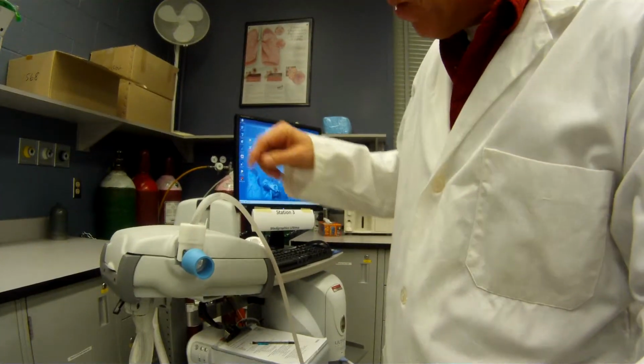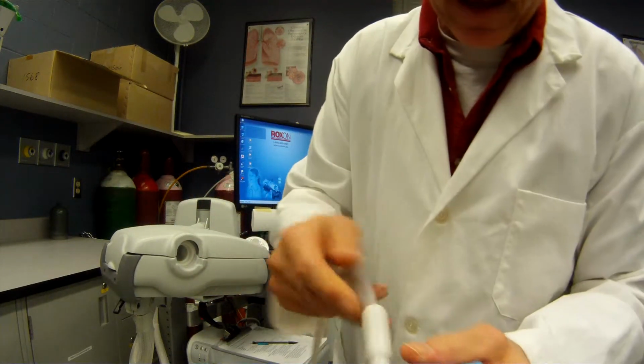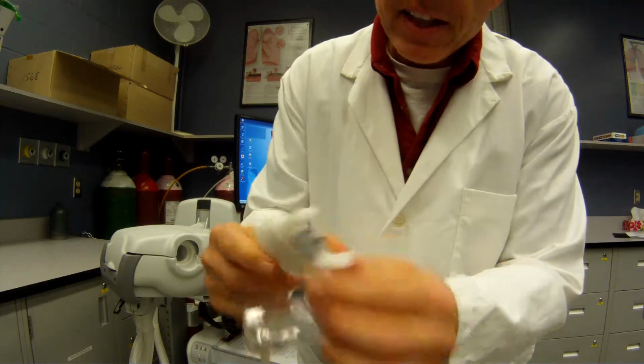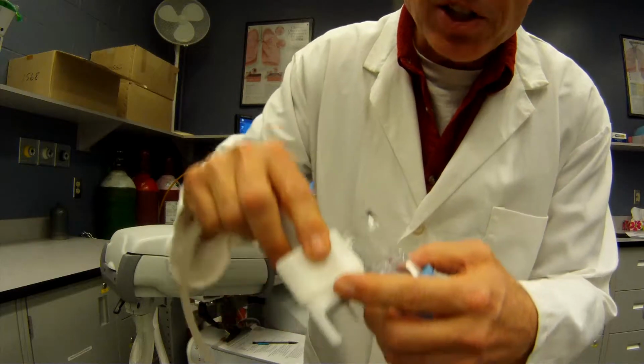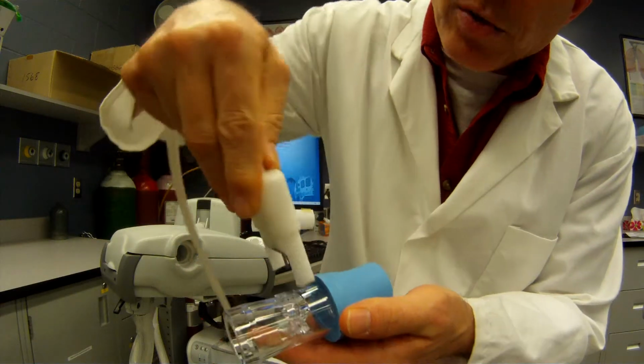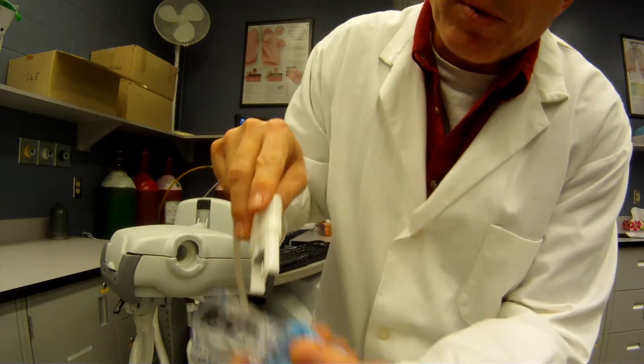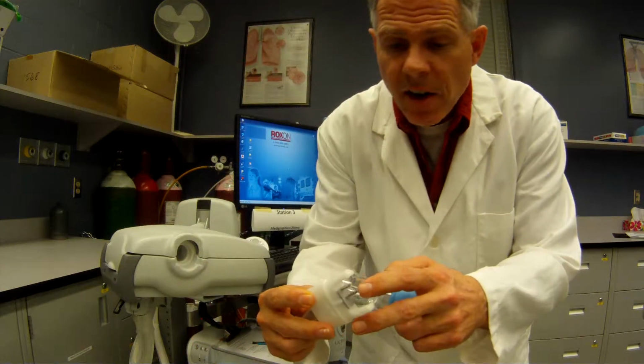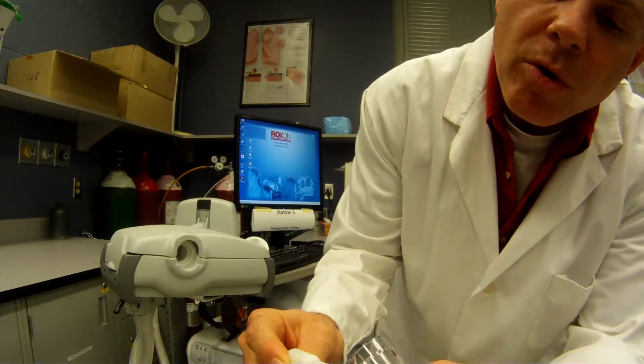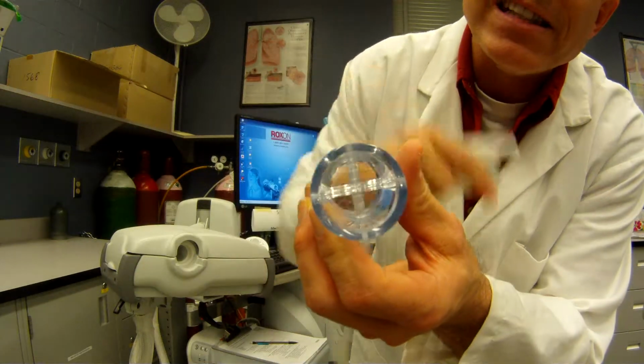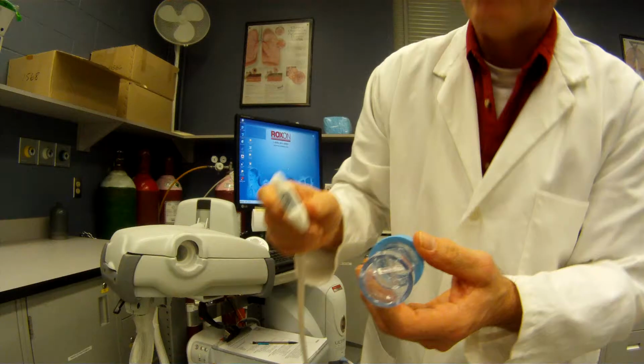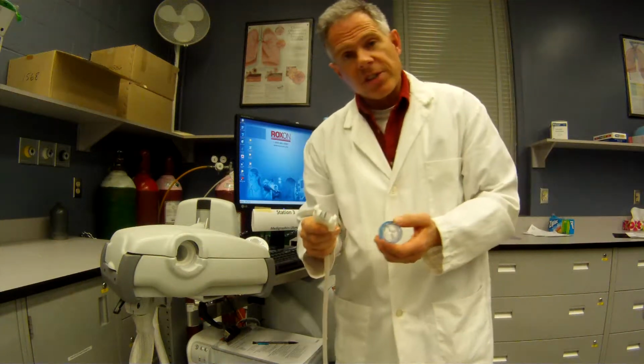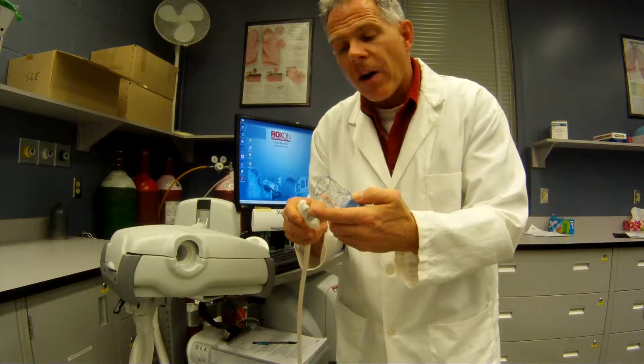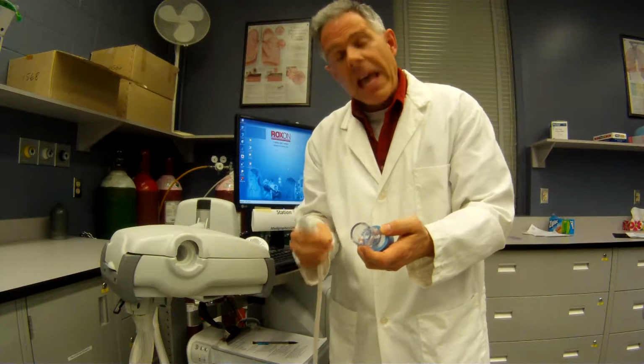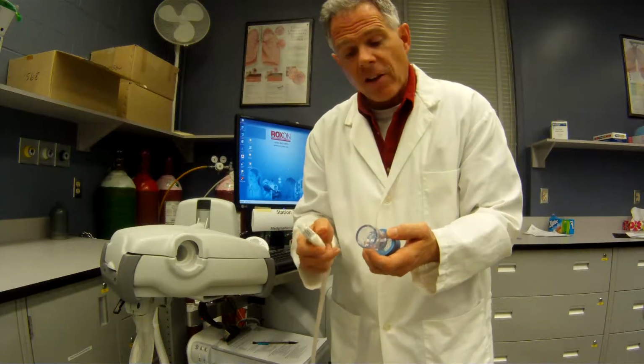Now, this little component right here is our pneumotach. And it's important that you plug this in correctly when you're hooking that up. There's a little notch in right here that has to line up with a little notch right here like that. And these little tubes have to line up with little holes also right in here. Now, this is the heart of the device. This is our pneumotach. And this pressure drop across here caused by that little bit of resistance inside there is how this device measures flow and pressures and volumes. By measuring the pressure drop across that known resistance, it can calculate the flow. If you know the flow for a specific period of time, that tells you the volume.